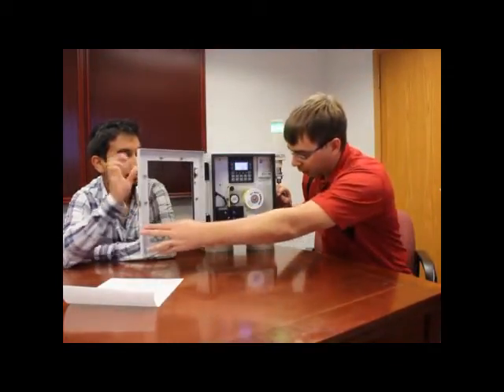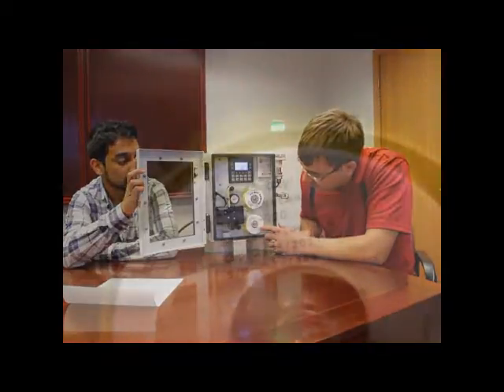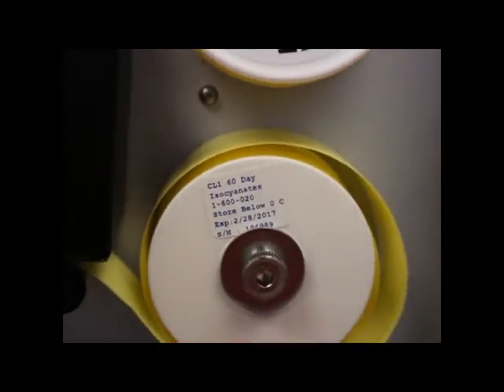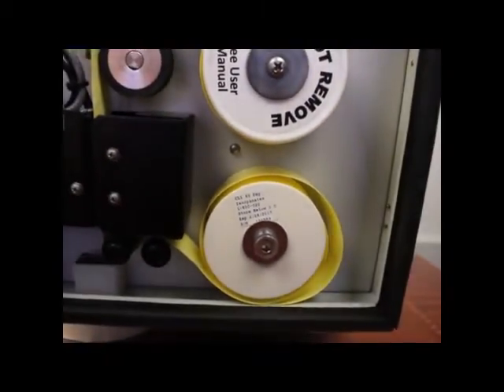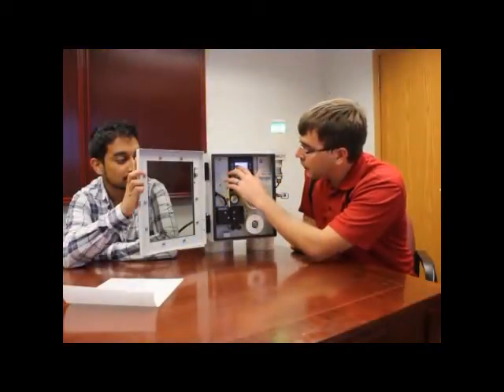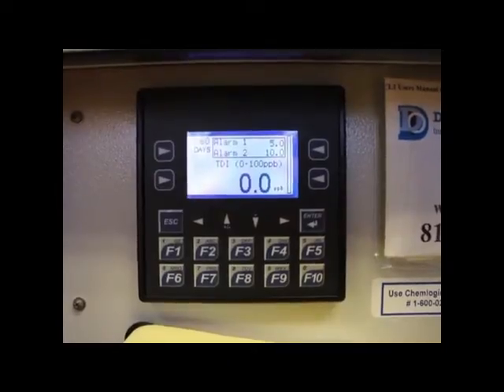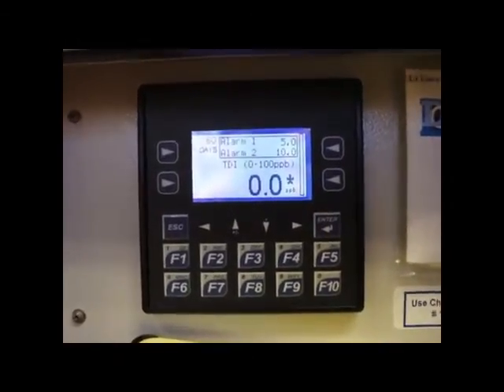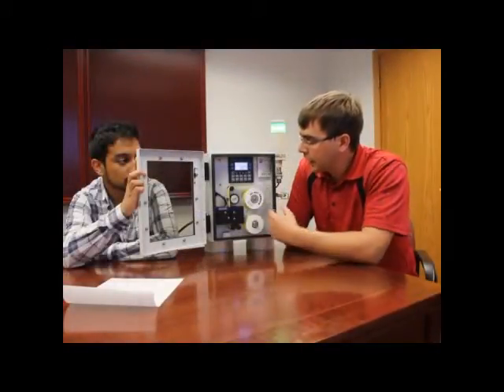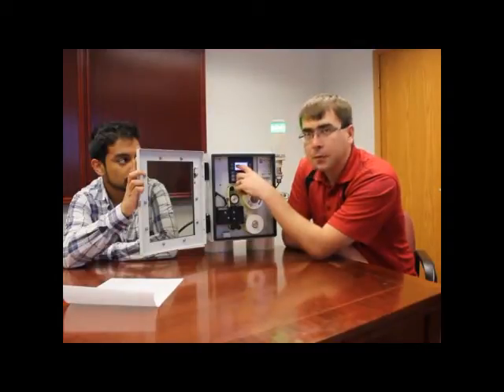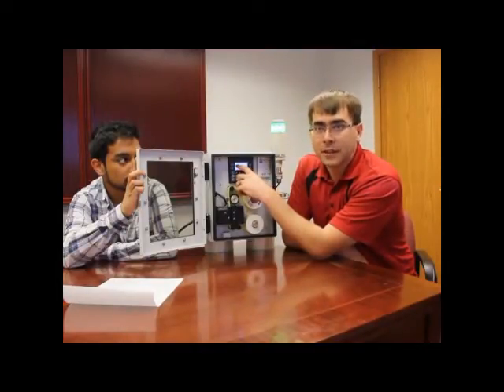The first thing we'll do is how to change the tape. There are two ways you know you need to change the tape: there's an expiration date posted on every one of these, so when the tape is expired, we know it needs to be changed. And if you look in the corner, it says 60 days. The tape, once installed, is good for 60 days outside of a refrigerator. If this countdown gets to 0, it's gone too long and needs to be changed.